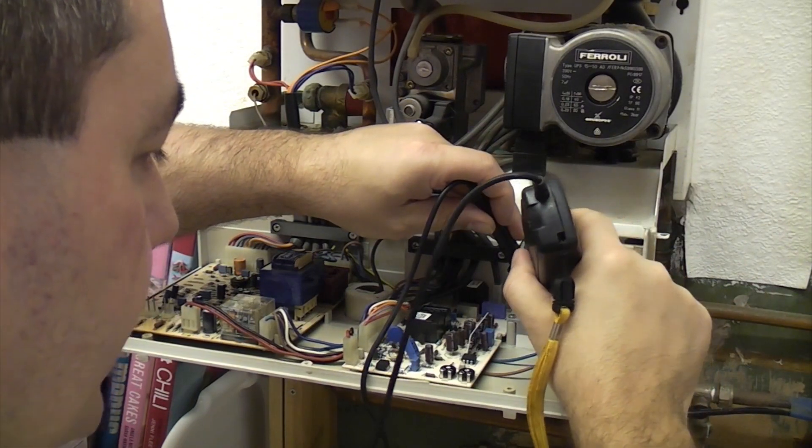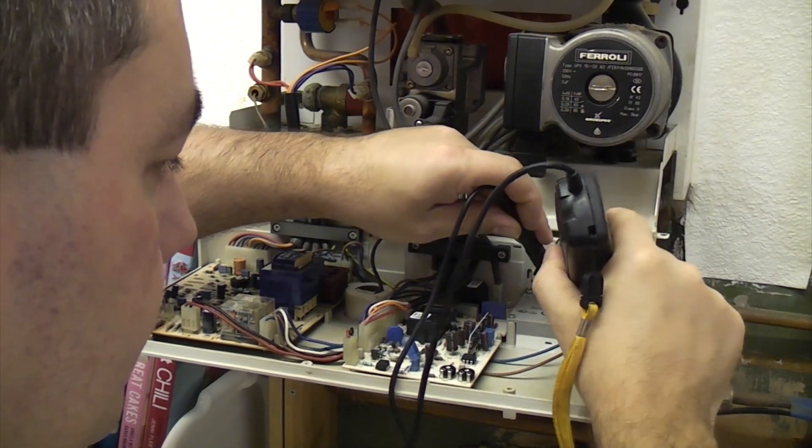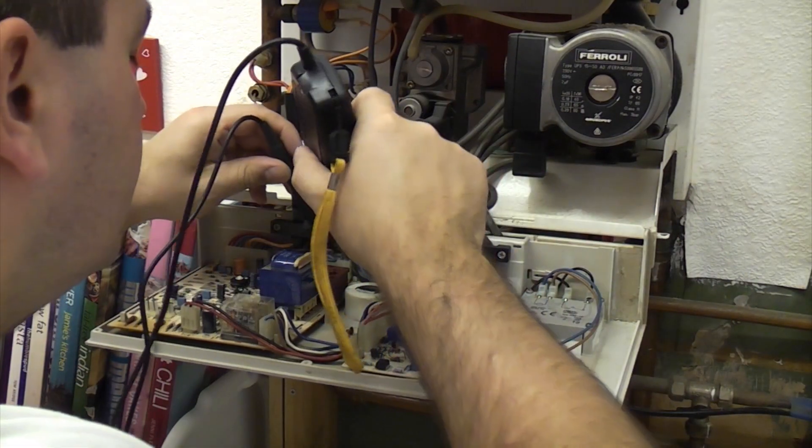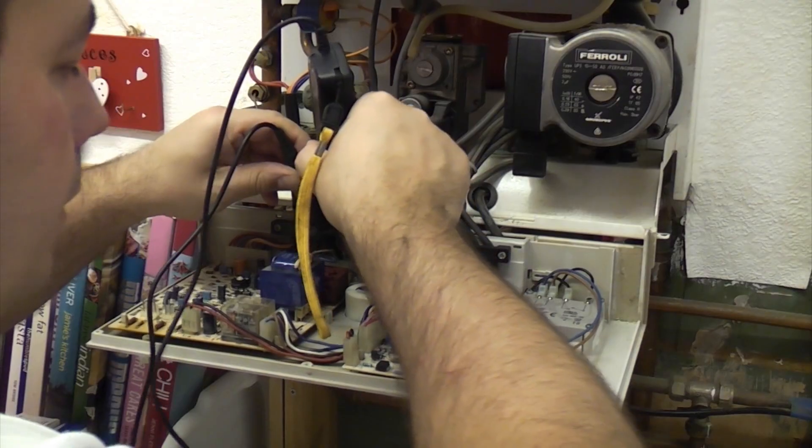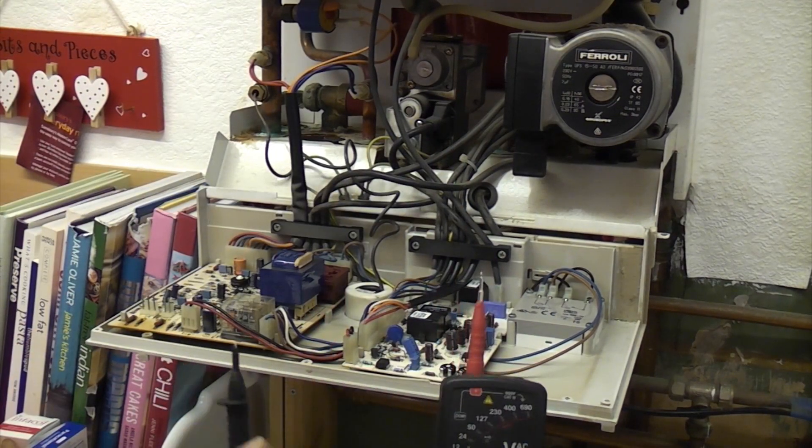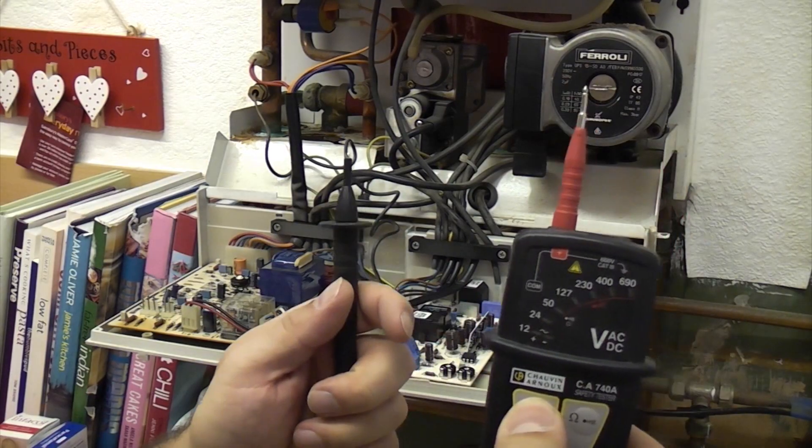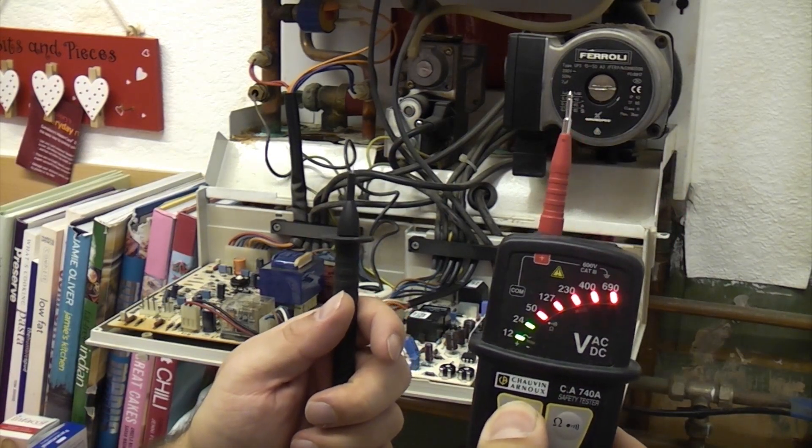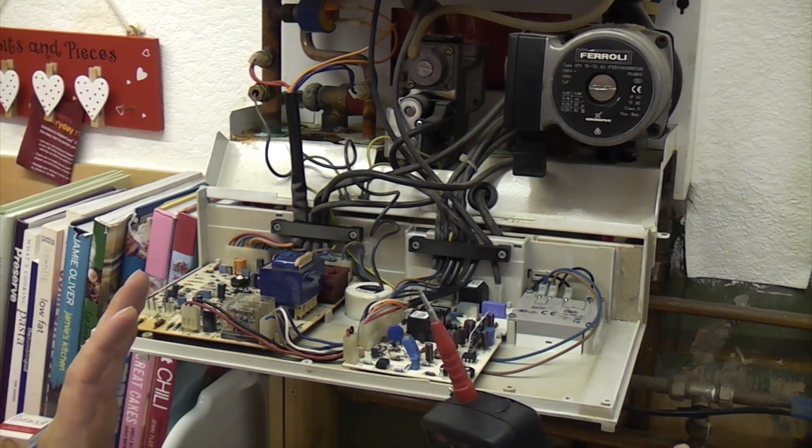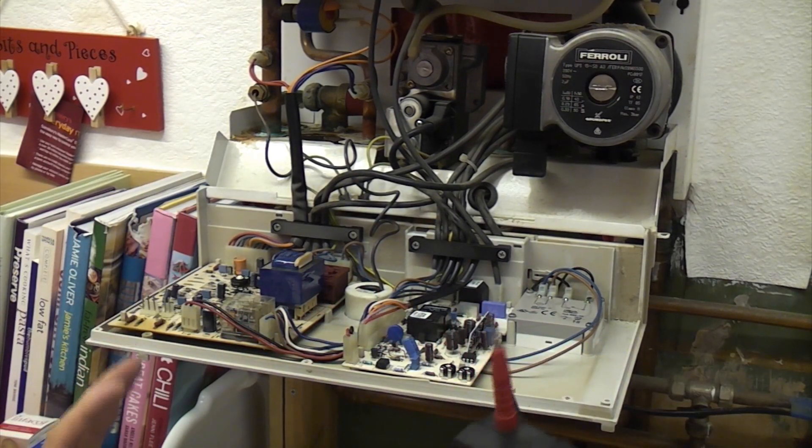So all we need to do is probe some of the terminals. So we can be confident now that that is actually dead and isolated correctly. So we are just going to test the tester again. So now we know that is working, so now we know that we can work on this quite safely without fear of anything being live at all.